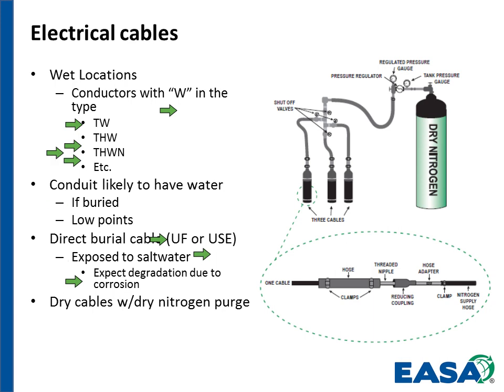In most cases of these types of things we're looking at here, one thing that's a pretty simple procedure is to use a dry nitrogen tank, connect that through a pressure gauge and regulator, and low pressure dry nitrogen literally being pushed through the cable. So you can push cable quite long distances. This is something you may even see in rural areas way out in the boonies, where you'll see a nitrogen tank standing there beside a power line, where they're using dry nitrogen to just push dry nitrogen through the cable and keep it dry. So pretty simple thing to look at here.